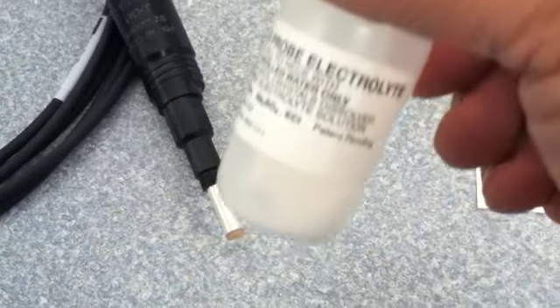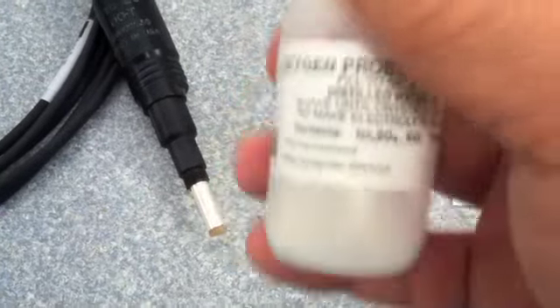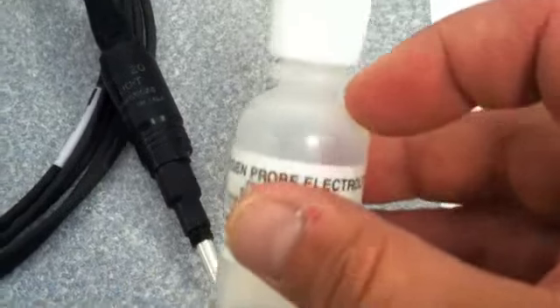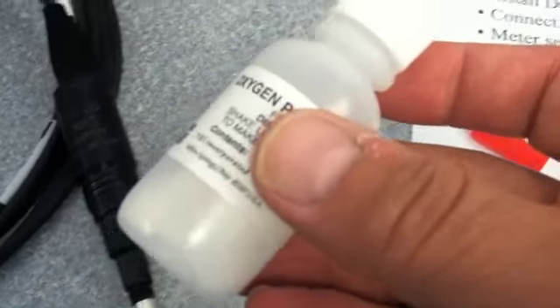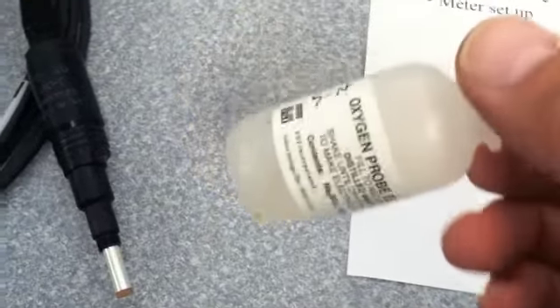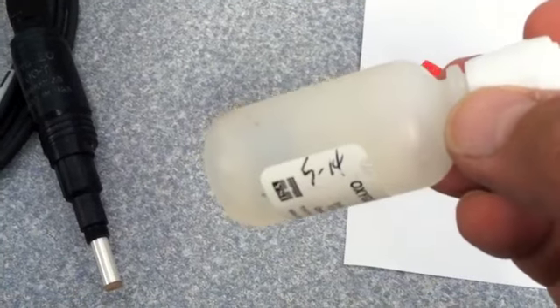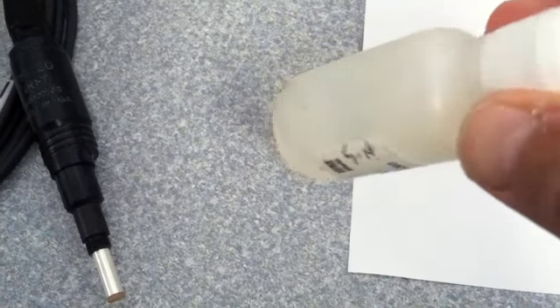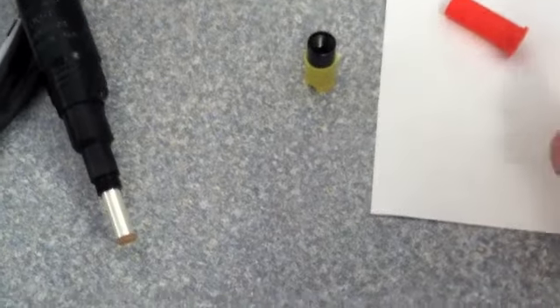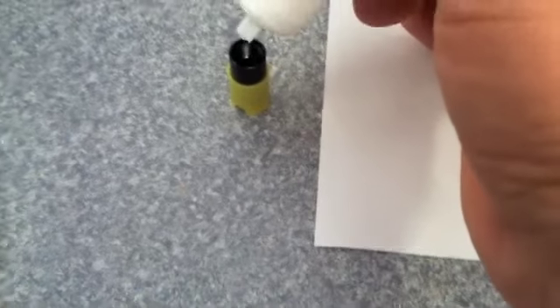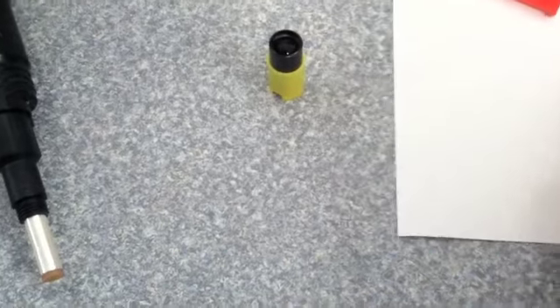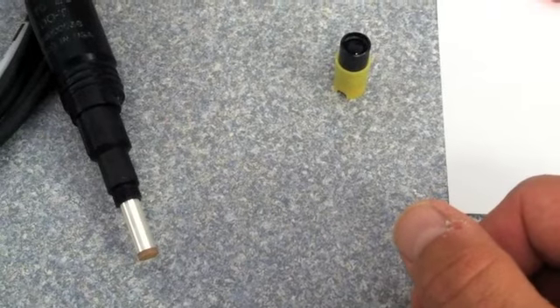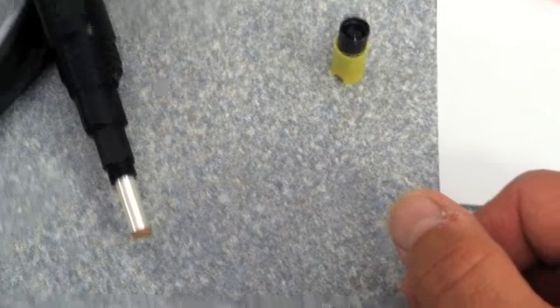In your box, you're going to get the electrolyte powder, and what you're going to have to do is initialize it, adding distilled water up to the top here, and you're going to want to let that set a while before you add it to the cap. Already have some solution that's made up. Once you make up your solution, it's going to be good for about a year, so you might want to put a date on it so you don't use expired solution. And then what you're going to do is you're going to take your cap and you're just going to fill it just above the threads, and any excess will flow out when you install the cap, so you're not going to have any air bubbles in it.